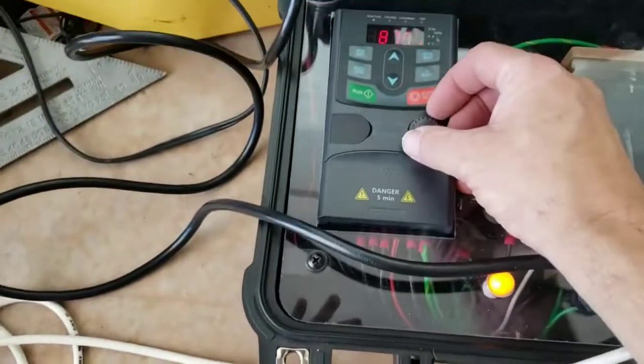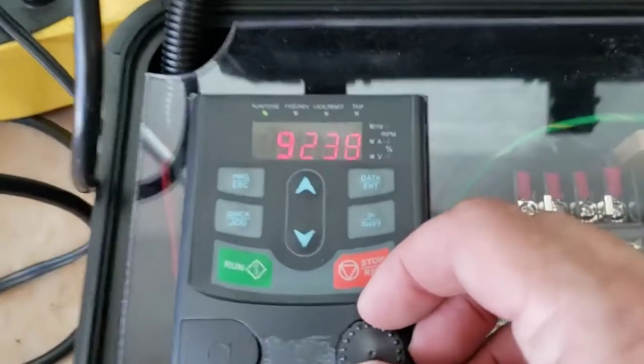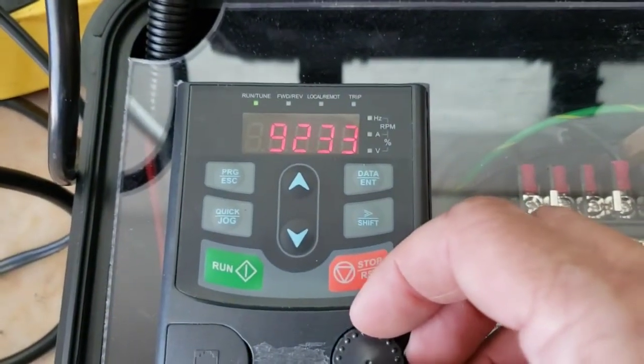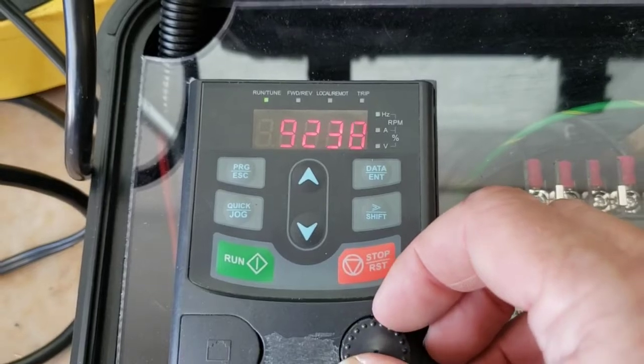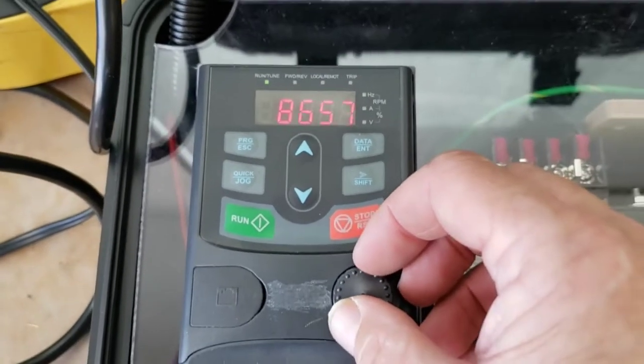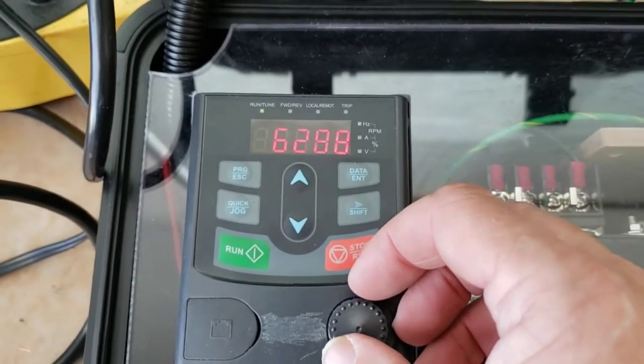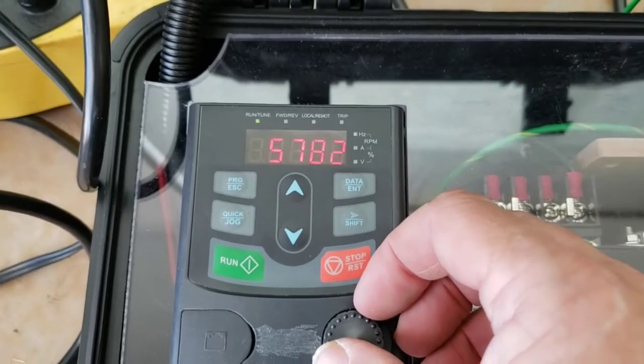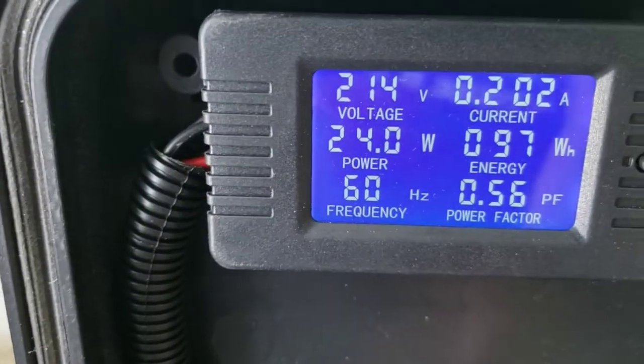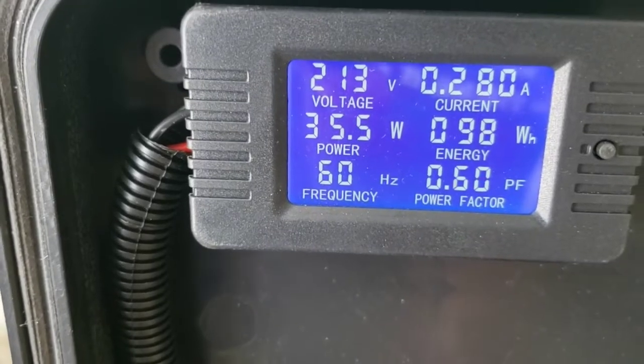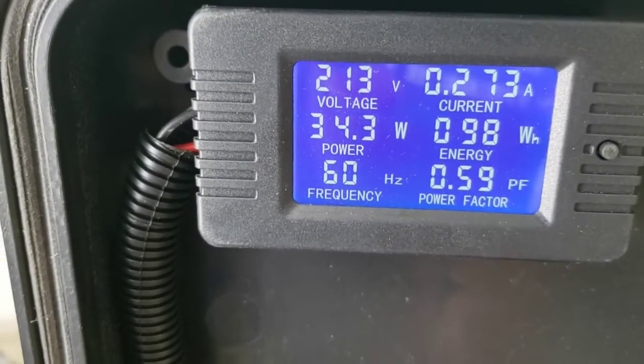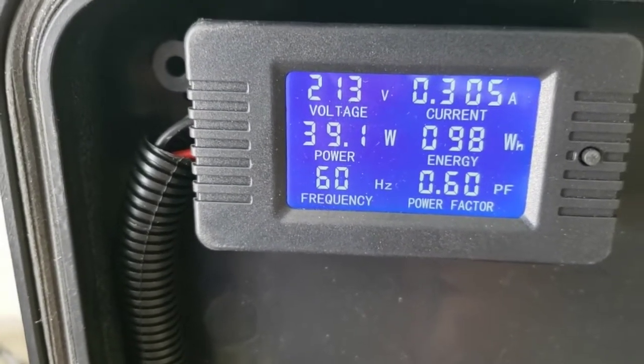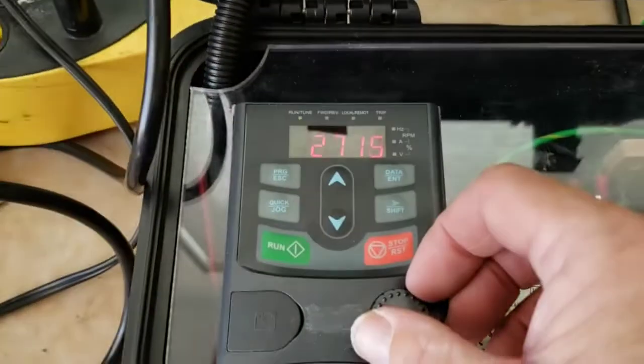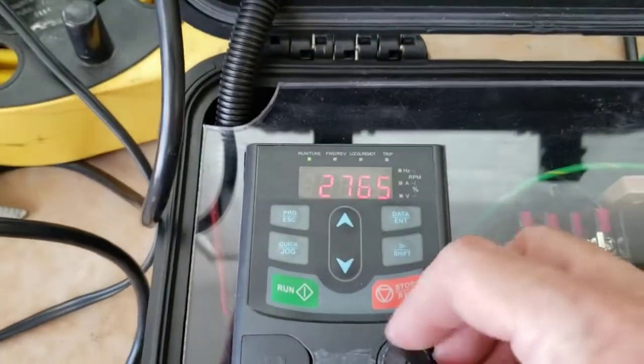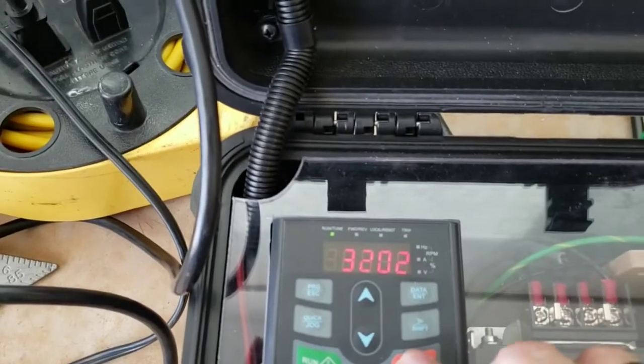This one, we've got a pretty good arc going on inside of that. And you watch the frequency, and the frequency is going to go crazy. As I turn up the power, frequency is just plummeting. See that? And the wattage is all over, jumping around, it's low. See, I'm at maximum power now. I'm only making 39 watts. Frequency's down to 2700 hertz. So clearly a bad cell.